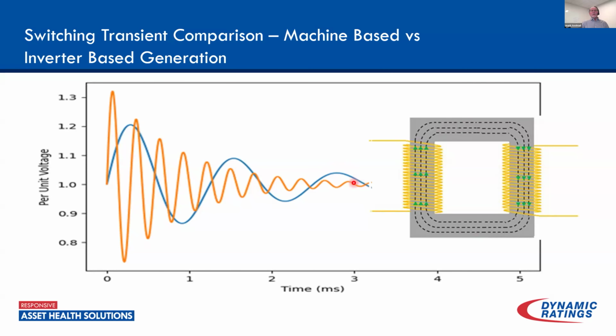The frequency of that transient was much less than what we're seeing with the inverter base. With the inverter base, we're seeing much steeper wavefronts and much higher per unit values when it comes to those switching transients. So here we're exceeding 1.3 per unit. And the frequency is what's really surprising me, because you're not hitting that insulation with that transient one time, you're hitting it multiple times over the course of a very short duration.